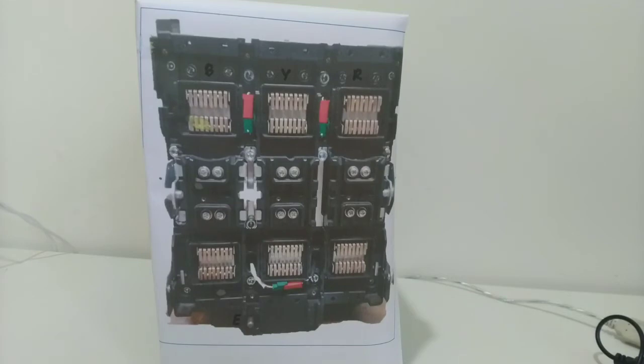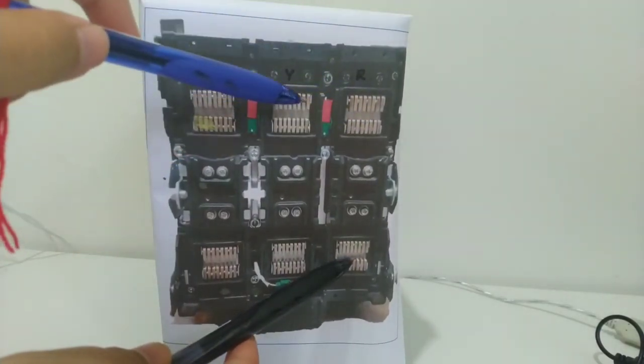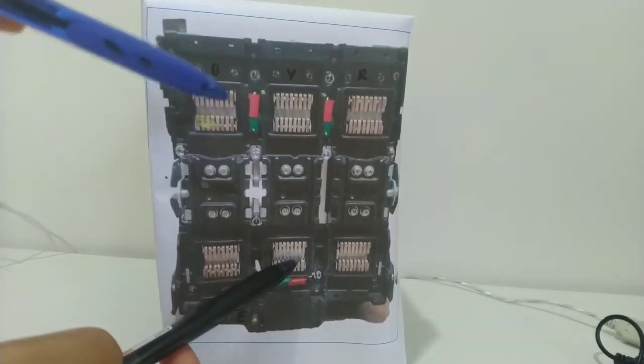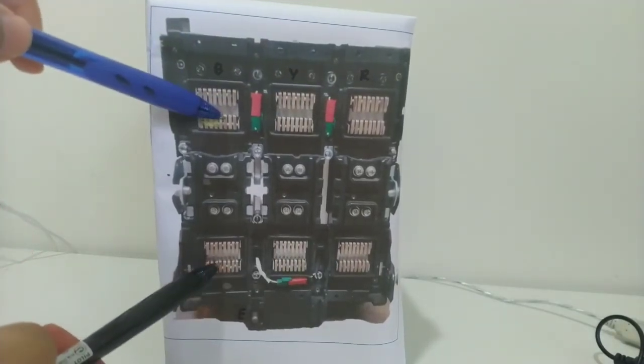Next, we do phase to earth: red to red, hold the test button, then yellow to yellow, hold the test button, blue to blue, hold the test button until the reading comes up to the scale.